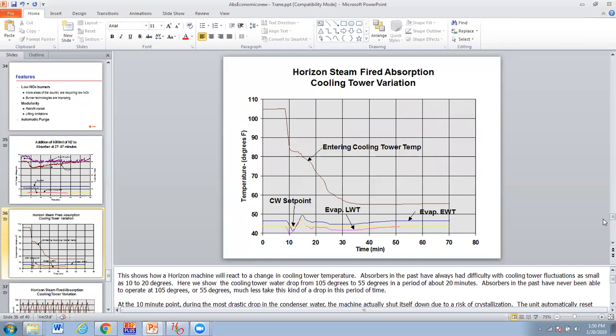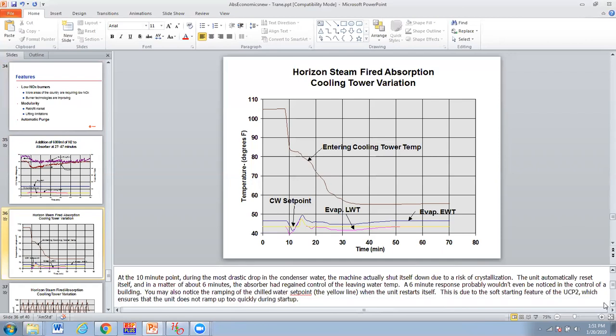Here, they're going to take the cooling tower, run it at 105, and then drop it to 55. Whoa, what is that, a 50-degree change in a period of 20 minutes? Absorbers in the past would never have been able to operate at 105 to start with, or 55, much less to take this kind of a drop in a short period of time. So at the 10-minute point, the most drastic drop in condenser water, the machine actually shuts itself down due to risk of crystallization. So here's our drop.